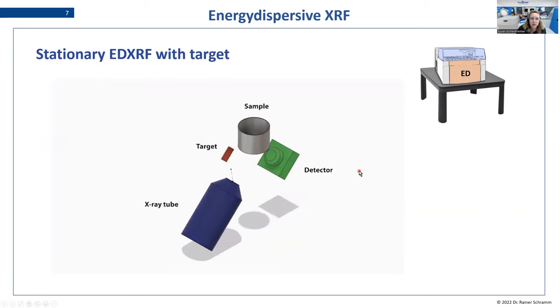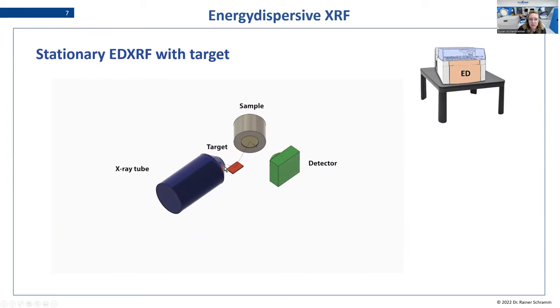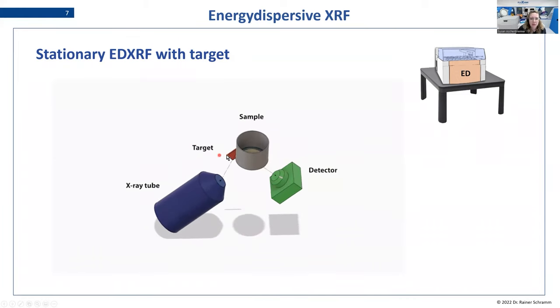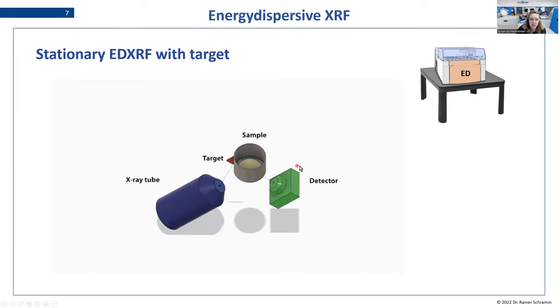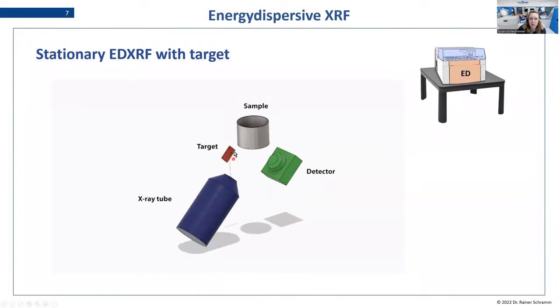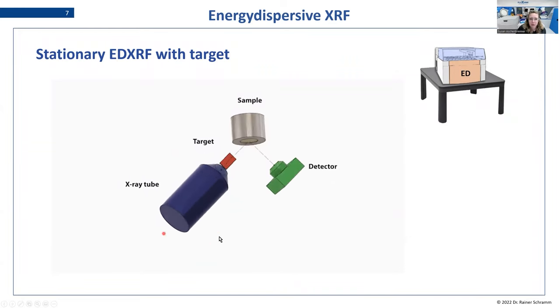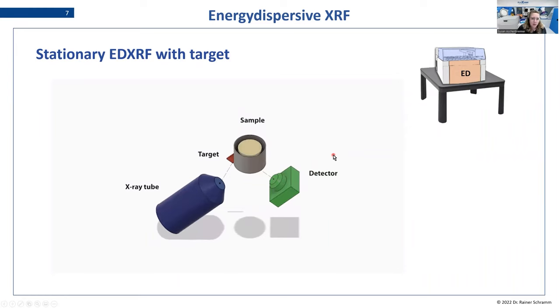The second way this can work is when we have a polarizer between the tube and the sample — here we have indirect excitation. The radiation from the X-ray tube first goes to a polarizer, also called a target, then from the target to the sample, and then to the detector. The thing with the target is that you can improve the peak-to-background ratio, especially in light matrices. However, you do lose a little bit of X-ray power because the radiation has to travel through the target and be polarized.